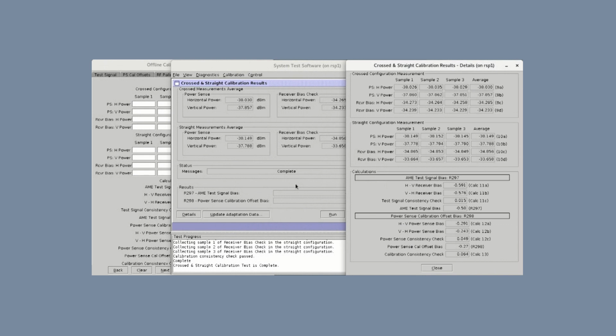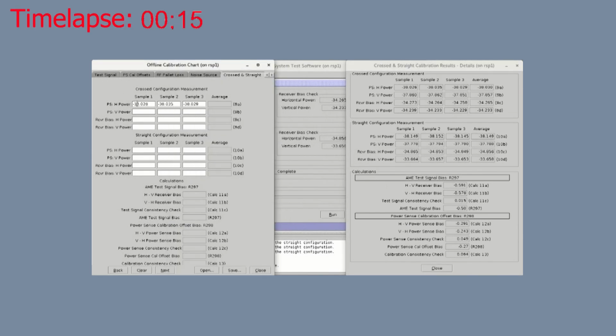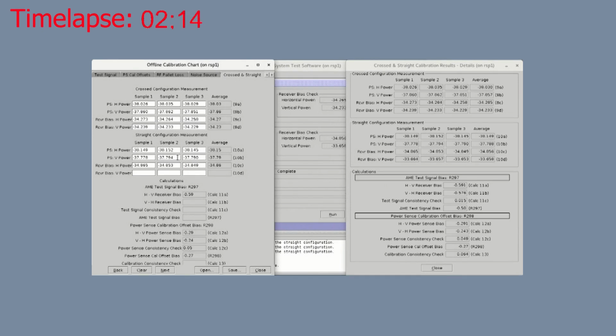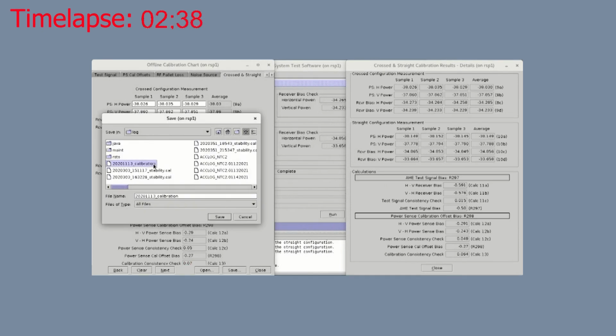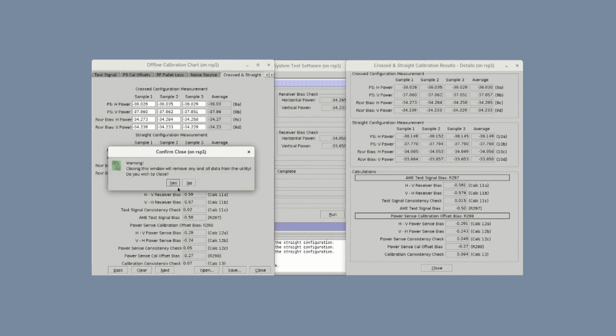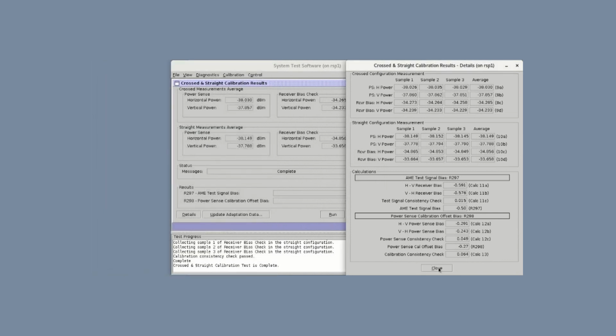Observe the following in the crossed and straight calibration results window. All fields are updated. The update adaptation data, run, and close buttons are activated. If the calibration is successful, the status field displays the message calibration consistency check passed. If the calculation values are acceptable, record the values in Table 619 RDA offline calibration worksheet. If you use the offline calibration chart, enter your data if you have not already done so, and then save your data. In the crossed and straight calibration results details window, click Close.